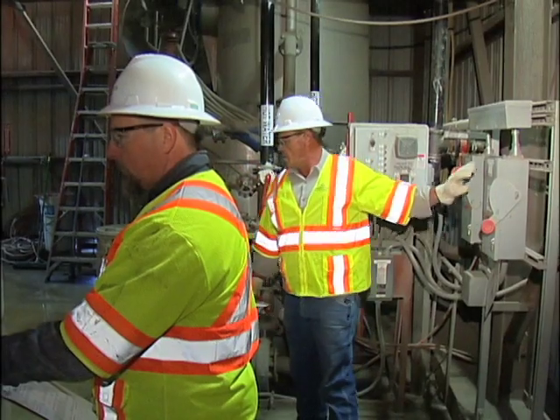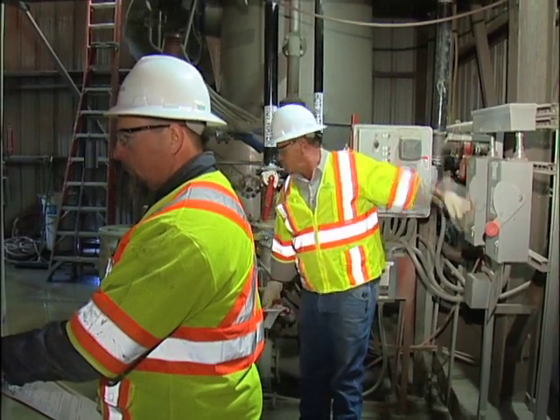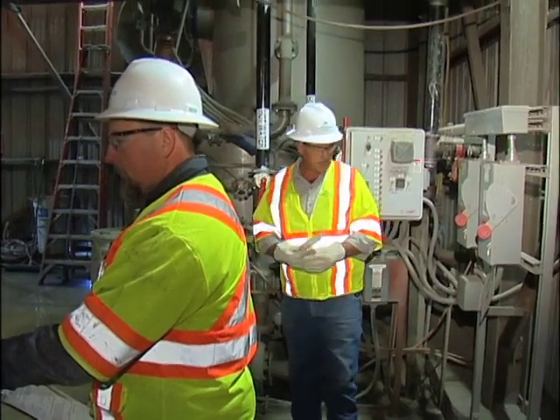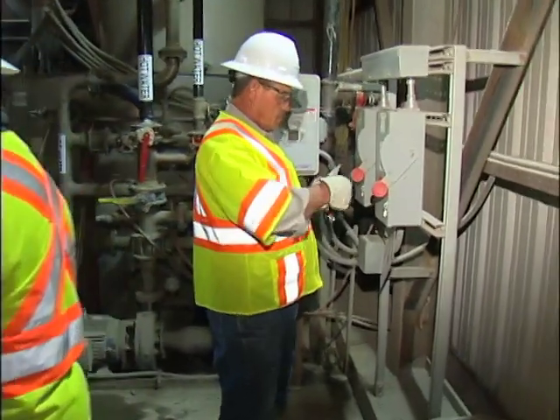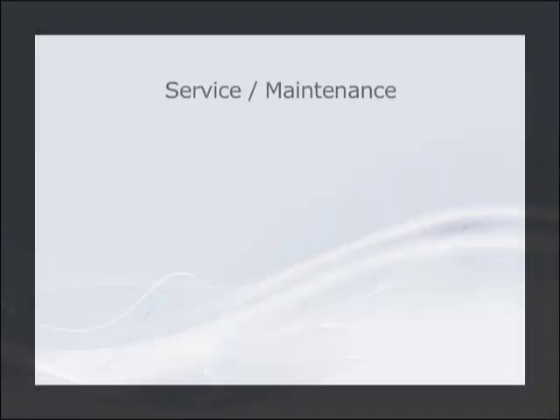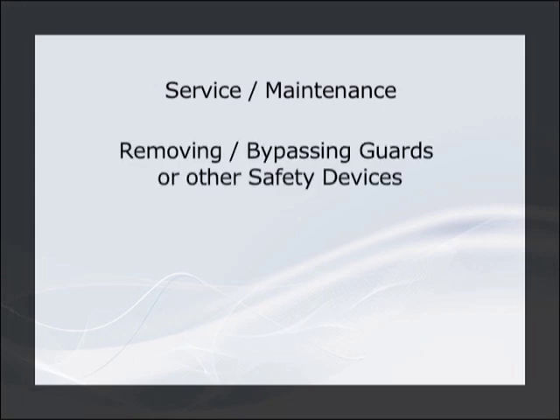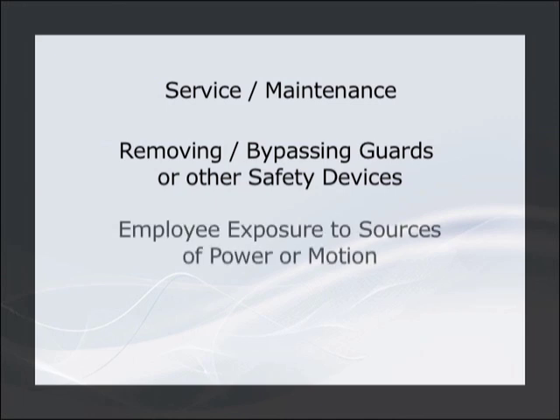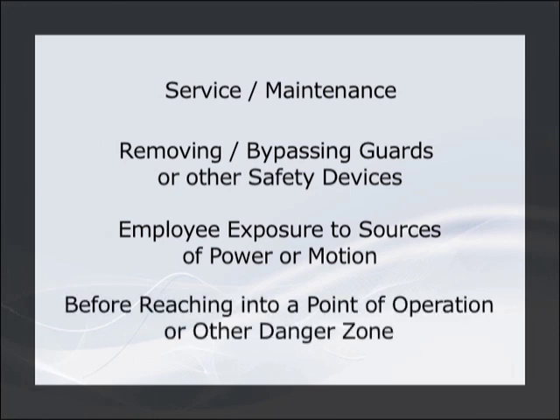These 4 employee task situations require that lockout, tagout, and tryout be applied before work can commence. Number 1, service or maintenance. Number 2, removing or bypassing guards or other safety devices. Number 3, employee exposure to sources of power or motion. And number 4, before reaching into a point of operation or other danger zone.